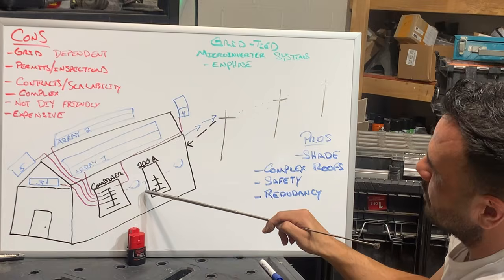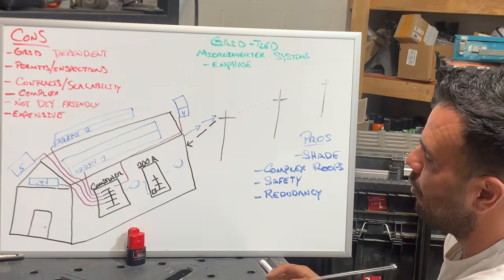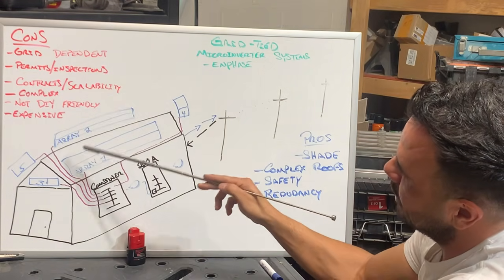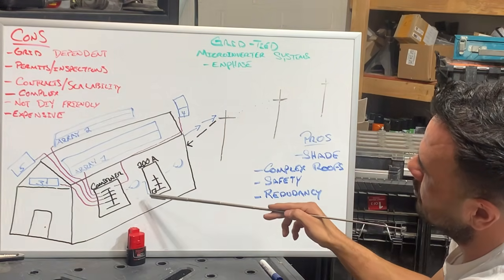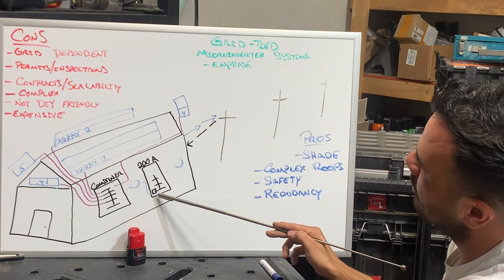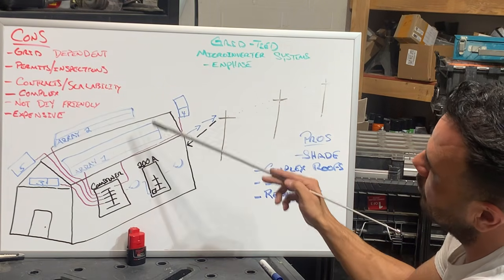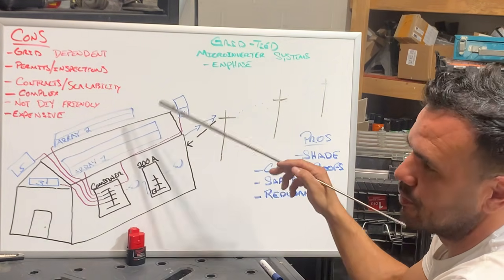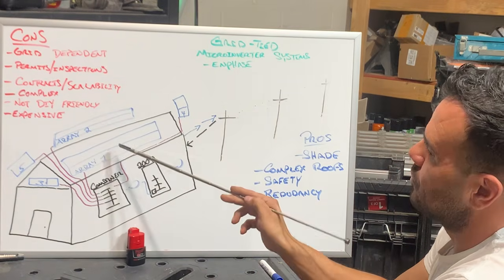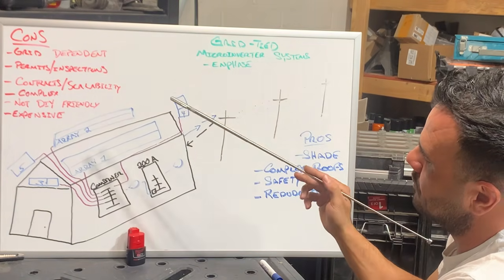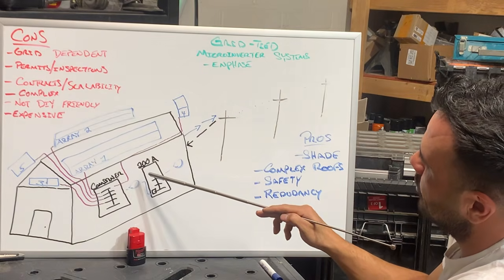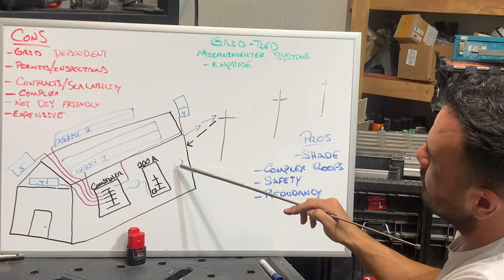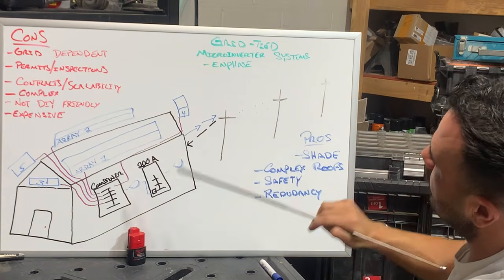And once it leaves the recording meter, it goes to a 30 amp double pole breaker inside of our main electrical panel. And so if we have 6,000 watts of alternating current coming from our combiner box to our 30 amp double pole, we have 3,000 watts going up this bus bar and 3,000 watts going up this bus bar. And just like our last example, if your house is using 3,000 watts of electricity, your solar is going to help you with all 3,000 watts, and then the other 3,000 watts you're going to export through this meter here. It's usually a bi-directional meter. This meter here allows you to export and sell electricity to the grid.